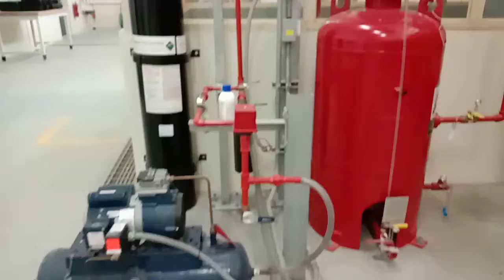Now again, the air is supplied all the way from the compressor. We have an air compressor here, and as backup support, we have a nitrogen cylinder. It supplies a pressure up to 1700 psi. So huge, right? It will work in case we have some problem with the air pressure to start. Okay, so now this is all about dry pipe.